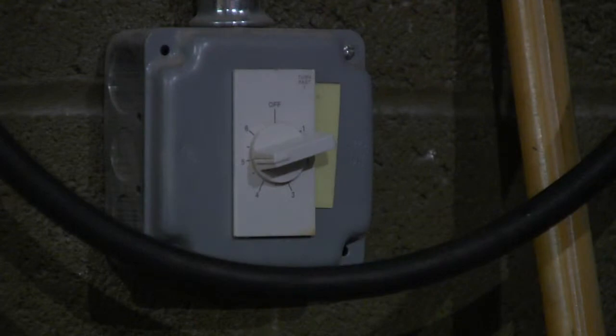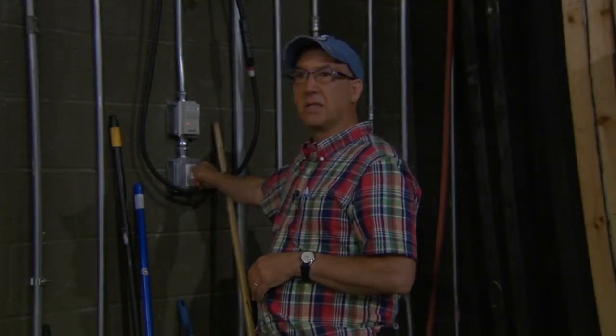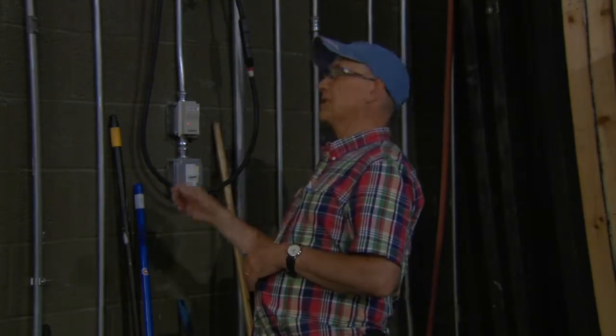Possibly. The other thing that I'm going to point out right here is there's an override timer. This is probably intended to be an override timer. So if someone comes in here after hours and the HVAC system's not running, they can turn this, and it's set up for 0 to 6 hours. I just clicked it to 1 hour.